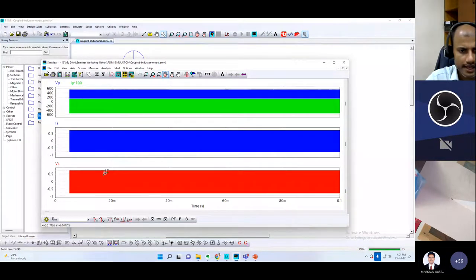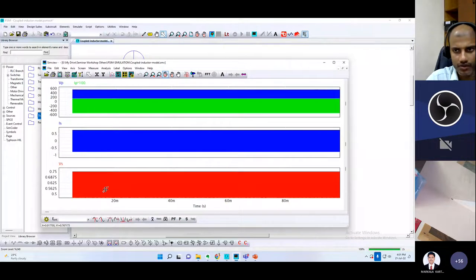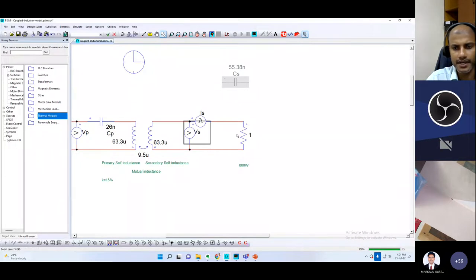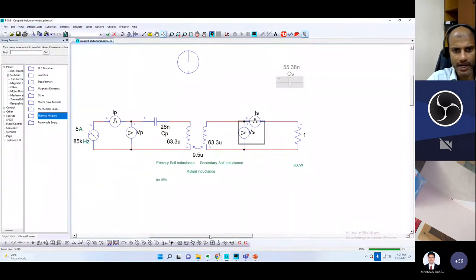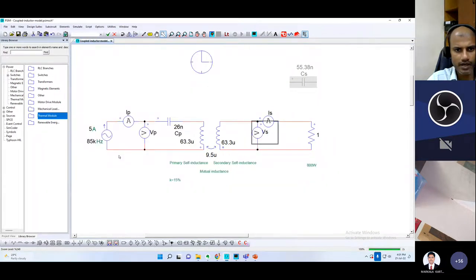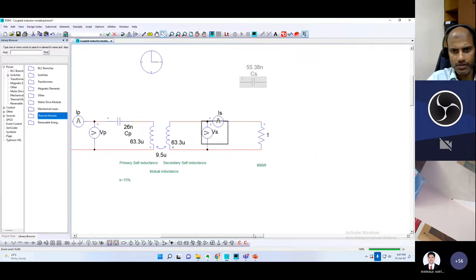But when we connected the load, it reduced to 0.75 volt. The voltage in the load side is just 0.75 volt, which is not sufficient for our application. Later I'll show you these parameters were obtained for a 400 volt to 48 volt battery charging system, so we cannot run a 48 volt battery with this system. The reason is that on the secondary side there is a lot of leakage, and once we connect the load, which is only 1 ohm, and current starts flowing, most of the induced voltage drop is across the leakage part.